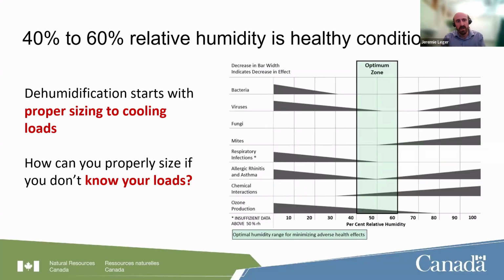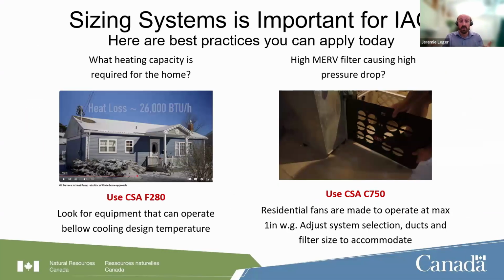Mostly in summertime, proper sizing of your equipment can get you good dehumidification without a dehumidifier, if you have an air conditioner or heat pump. But that requires properly sizing that equipment to the cooling loads, so we need to know the loads of your home to do this.